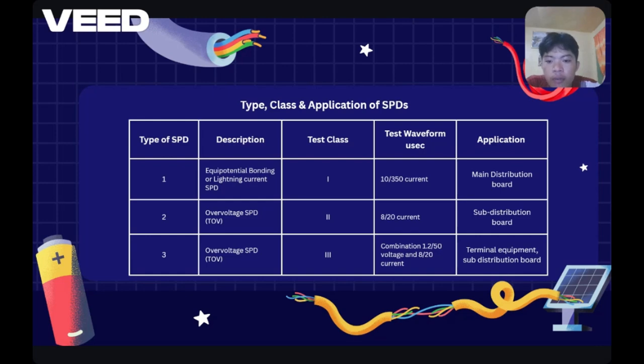Then next is overvoltage SPD, type 2. This is class 2, then 8 over 20 current. Then application is sub distribution board. Then overvoltage SPD, type 3. This is class 3, then combination of 1.2 over 50 voltage and 8 over 20 current. So application is terminal equipment, sub distribution board.